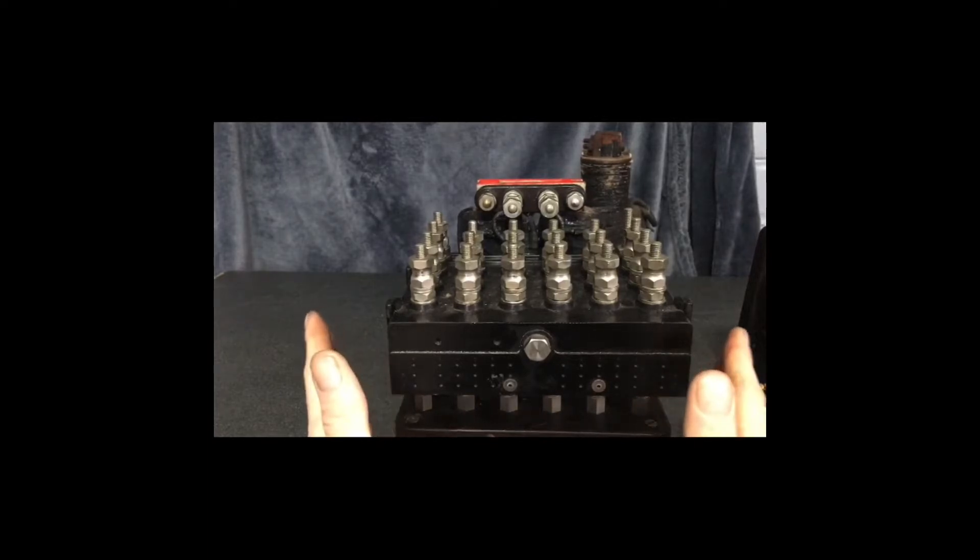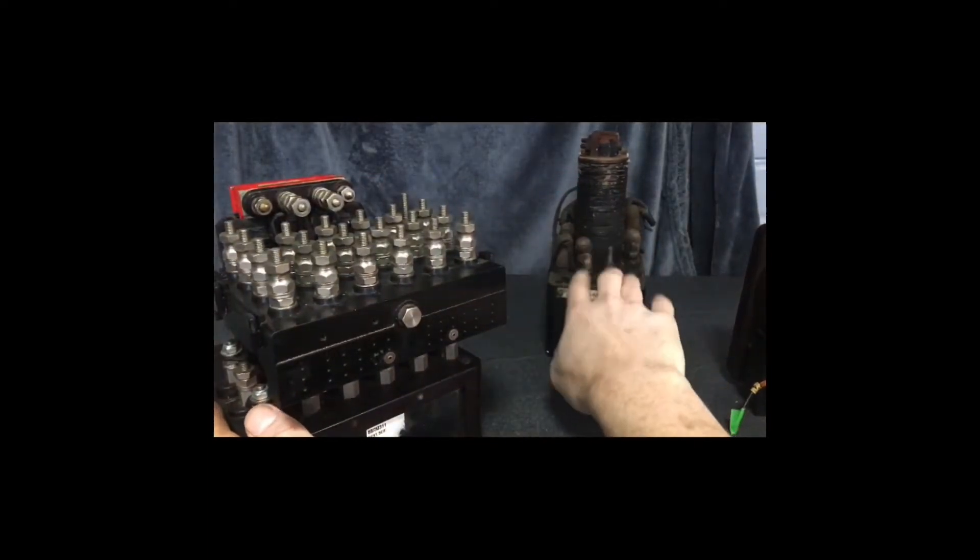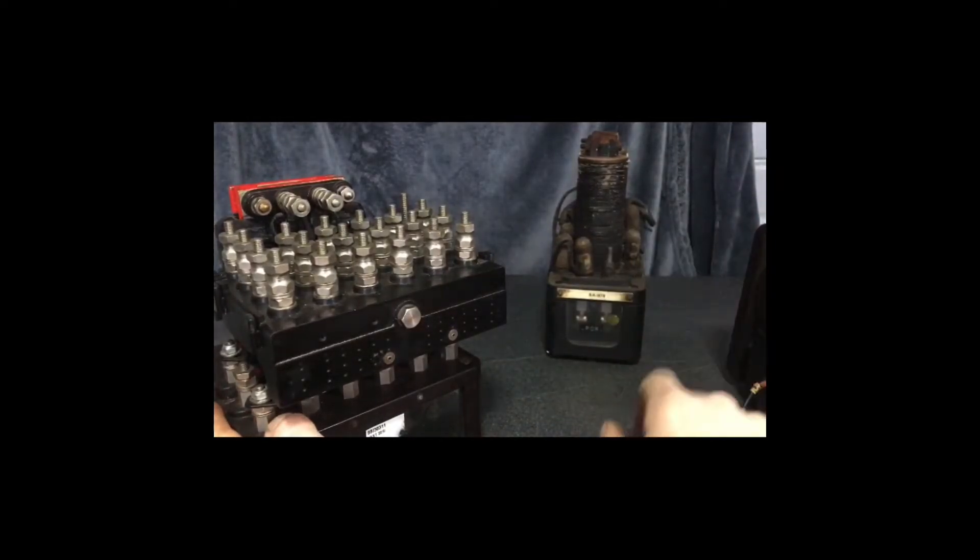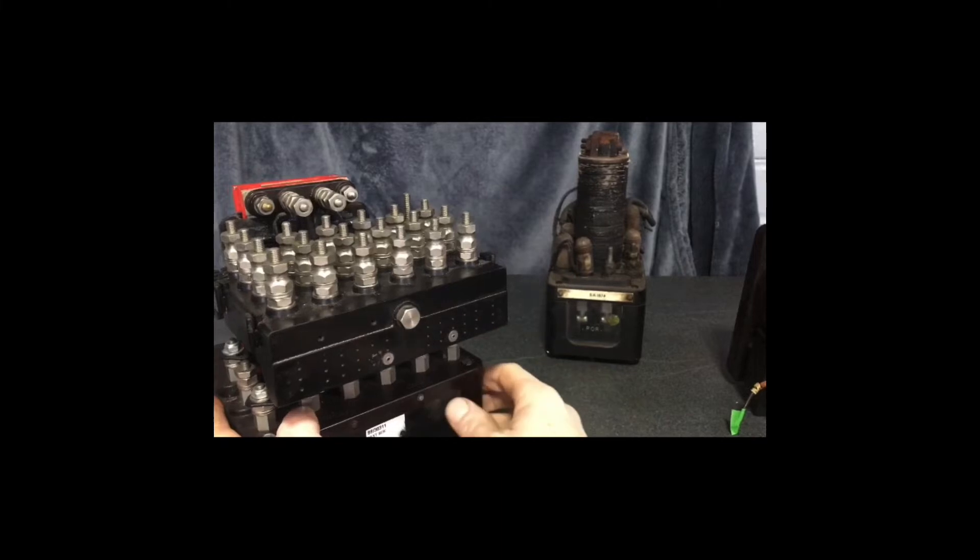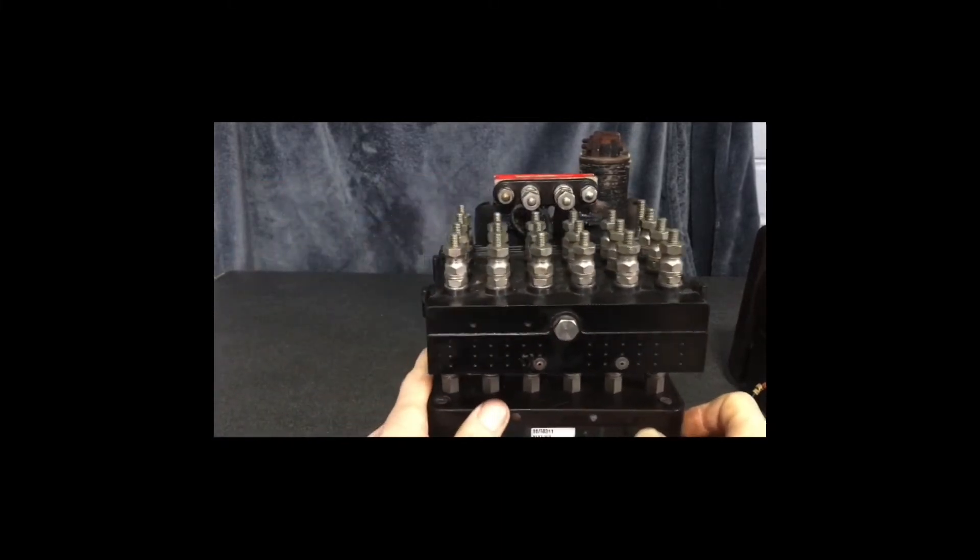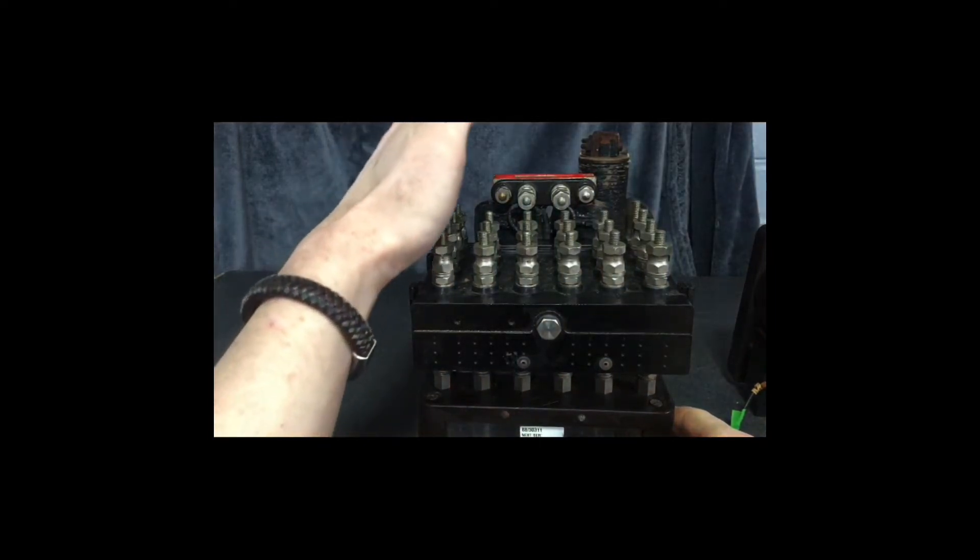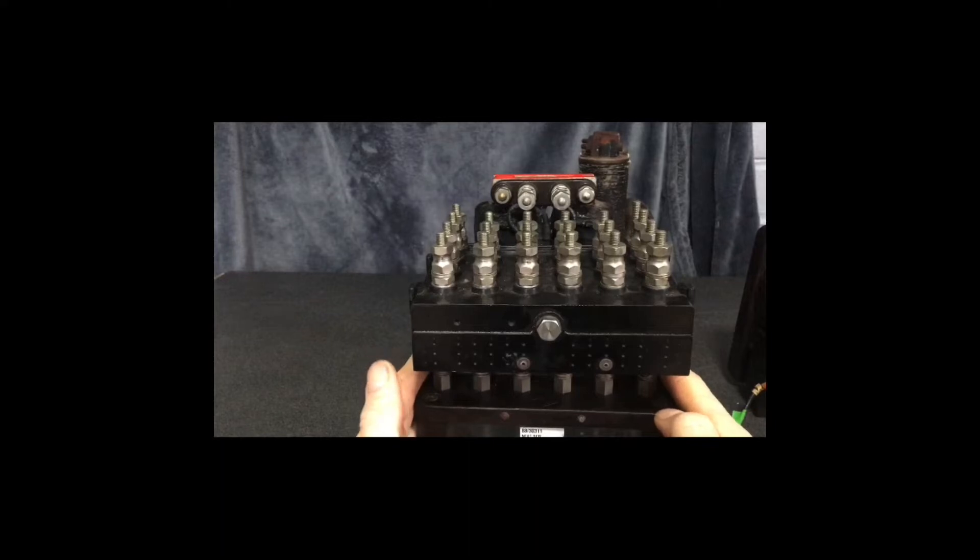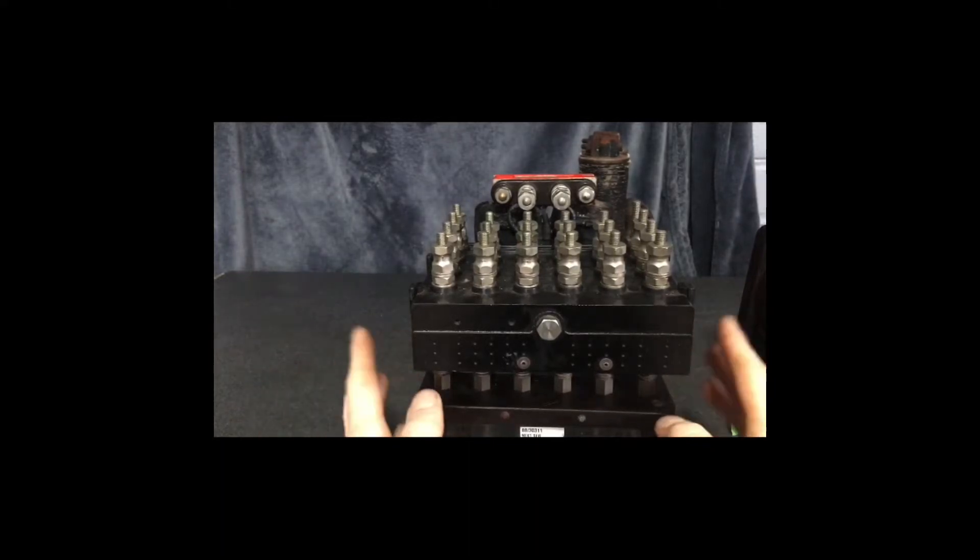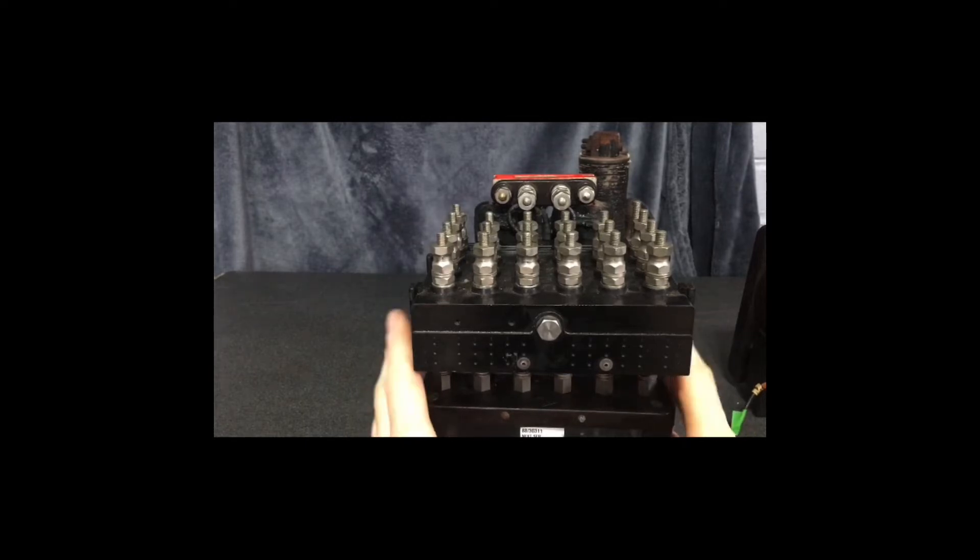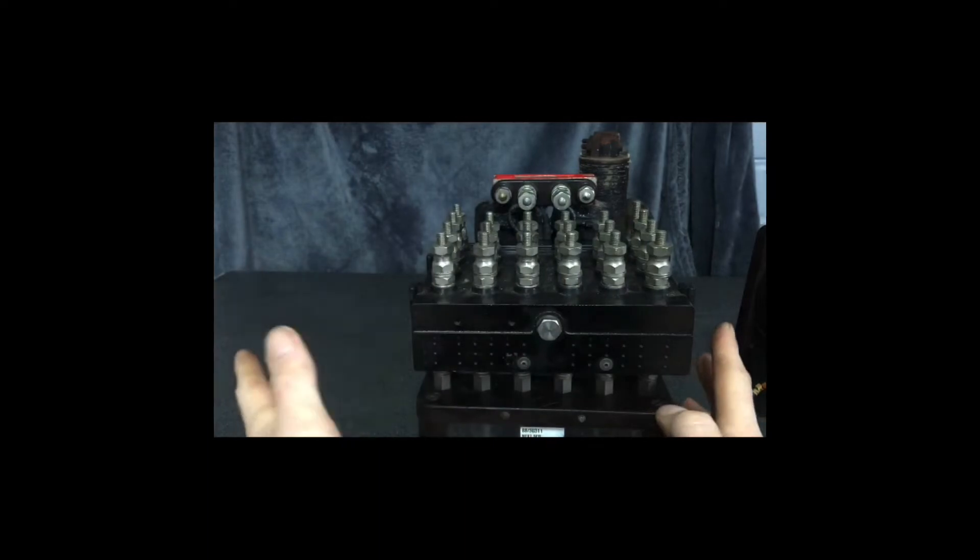If I was going to design a signal box, some of these circuits would be out in the cupboards doing lamp proving and such. But the actual interlocking, because that's run off a local battery or supply feed, these want to be run off a slightly higher voltage. So these are the interlocking relays. These can be run off 8 to 12 volts, a little higher. You don't want to go anywhere near 24 volts on these. You'll saturate the coils so they are magnetically stuck up.